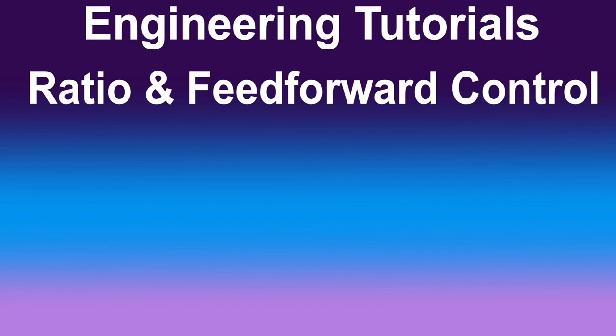Two-element feed-forward drum level application. Two-element feed-forward drum level involves two measurements, steam flow and feed water flow, to improve control accuracy. The feed-forward loop adjusts the feed water flow based on changes in steam flow.